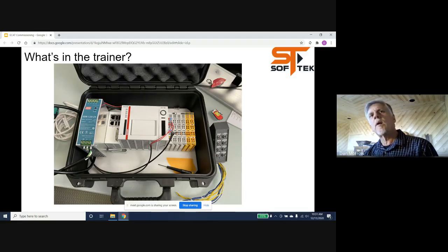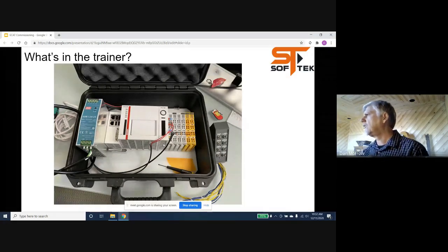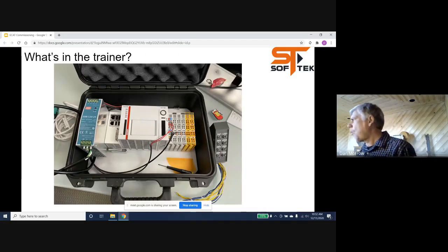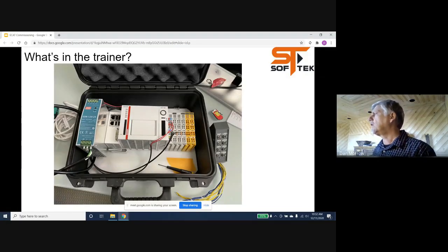The power for it comes in on this slice over on the left. There's a 24-volt input that runs the PC and all of the I/O slices bus, and then there's a second 24-volt link that runs the actual input-output and drives all of the field wiring on the slices. So it's not one hookup, it's two. Sometimes it's one power supply, sometimes it's two, depending on whether or not they want to disable I/O and leave the PC running.